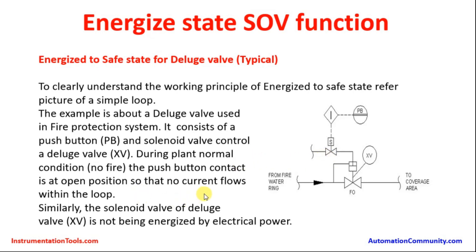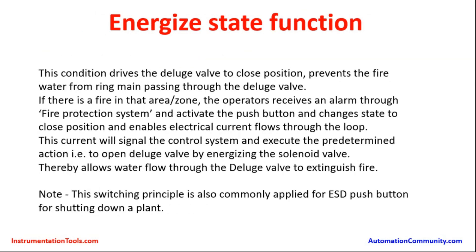The solenoid valve of the deluge valve is not being energized by electrical power, because only once the push button is pressed does current go through the solenoid valve. As long as the push button is at open position, no power goes to the solenoid valve of the main deluge valve. This condition drives the deluge valve to the closed position, preventing fire water from passing through it.